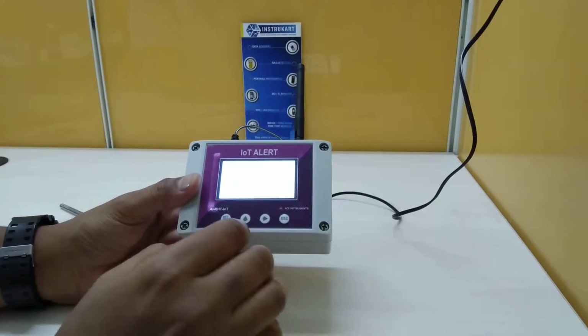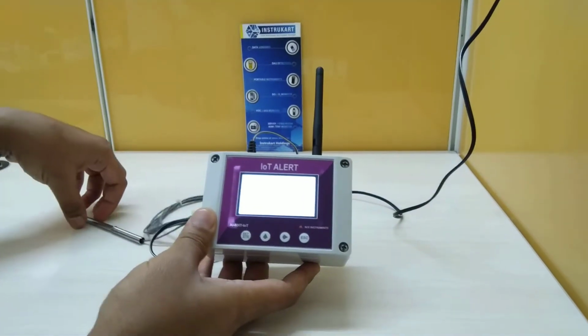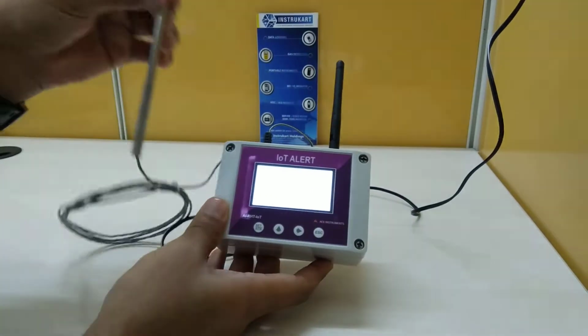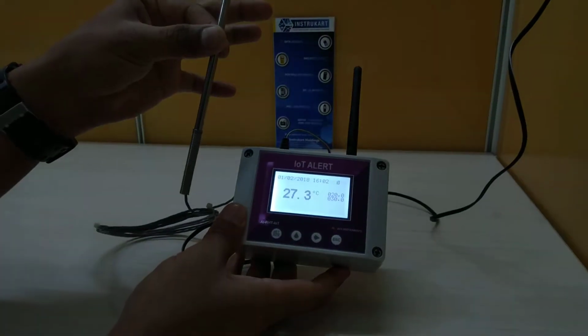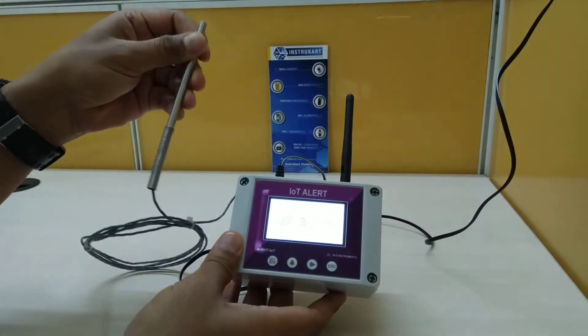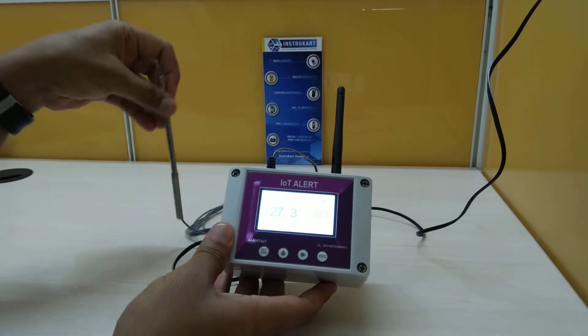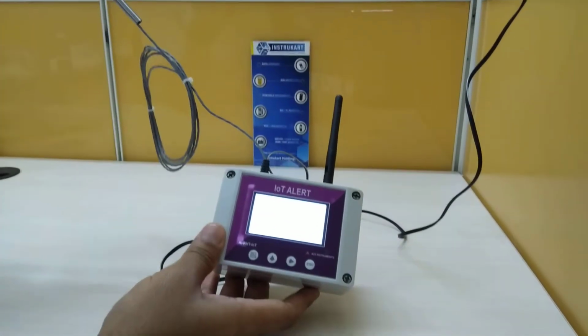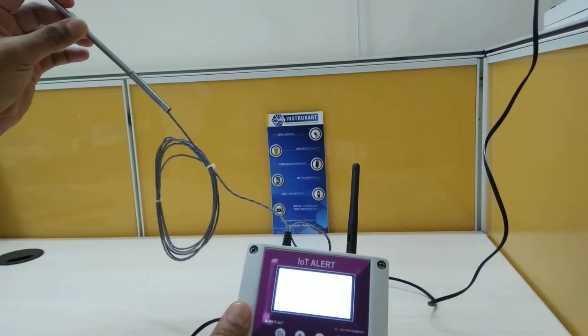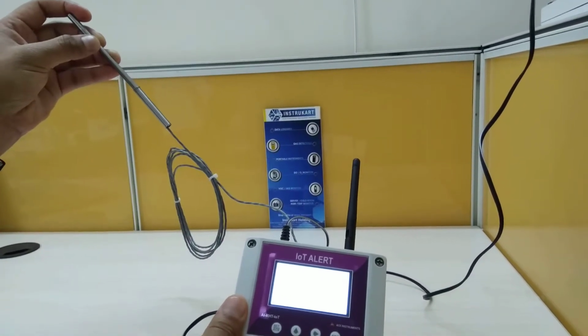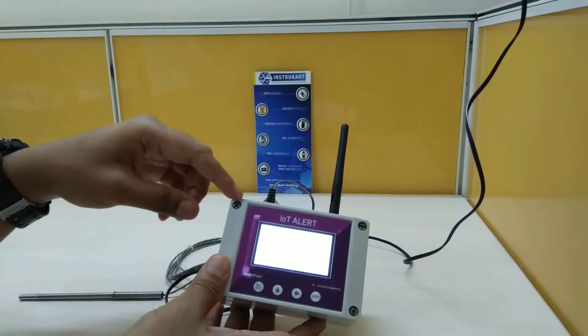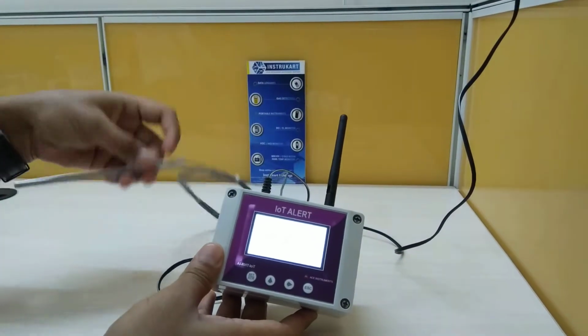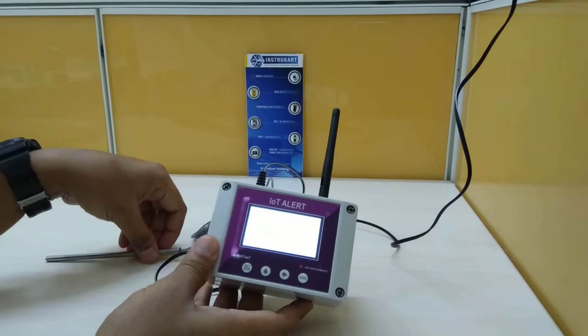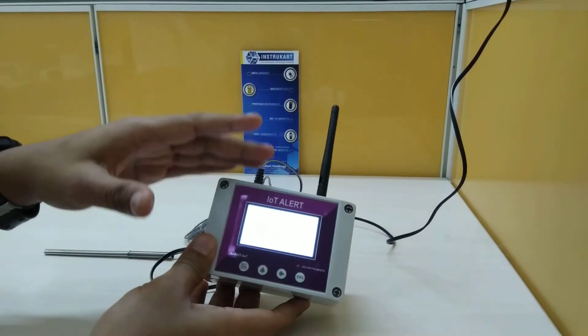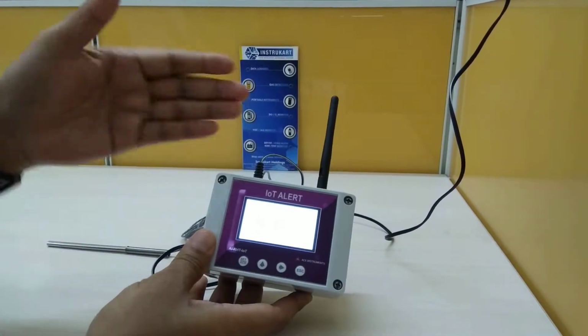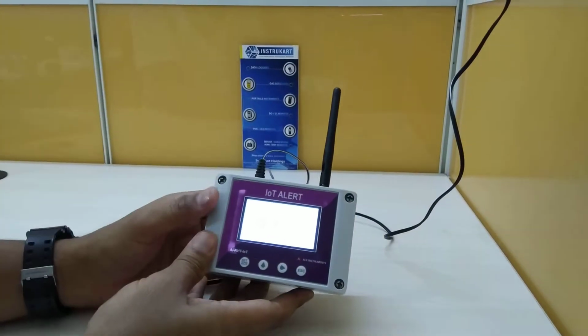The temperature range for this is minus 80 to plus 50. For that we have the sensor, and we can also have this sensor length extended to around 20 meters or 25 meters in case you want to put this monitor outside the room and put the sensor inside the server room or any data center, to check this monitor from your corridor itself while walking through.